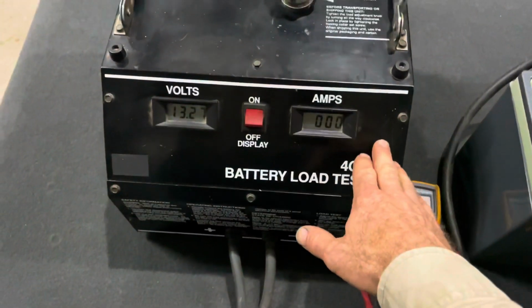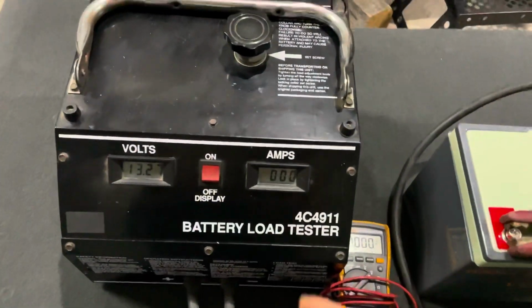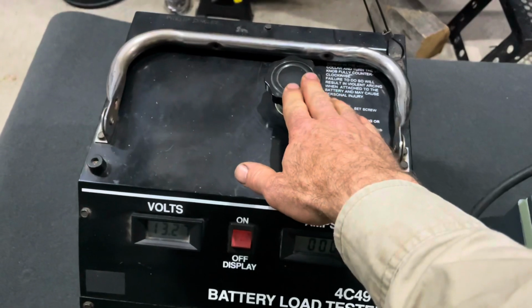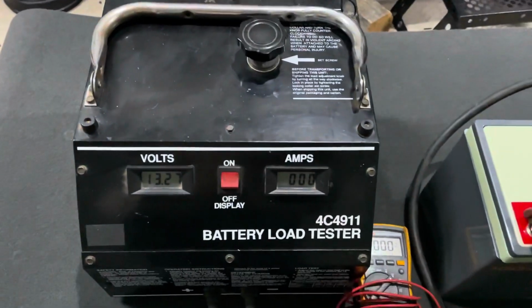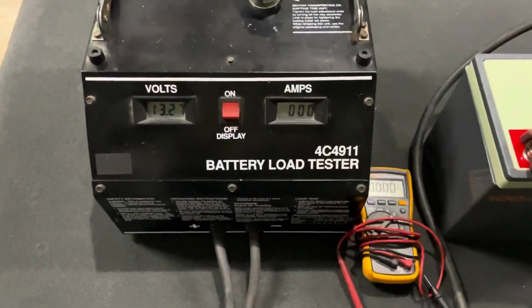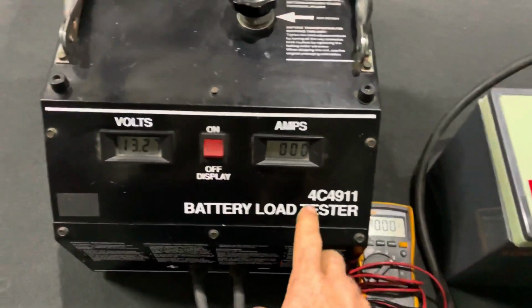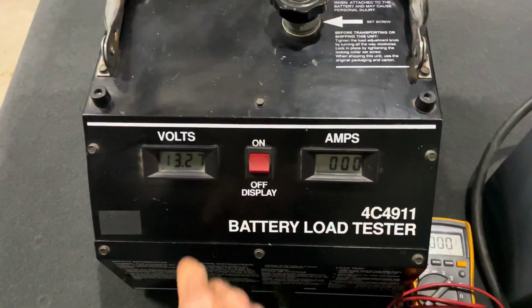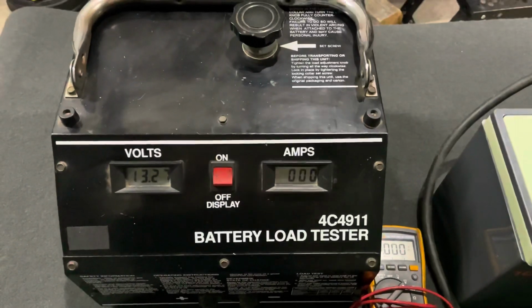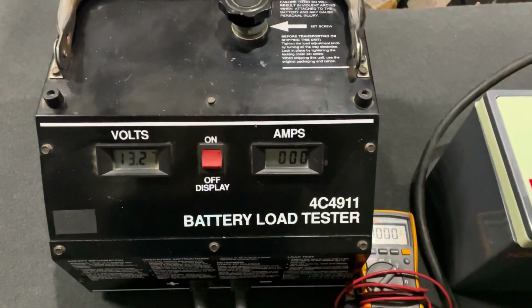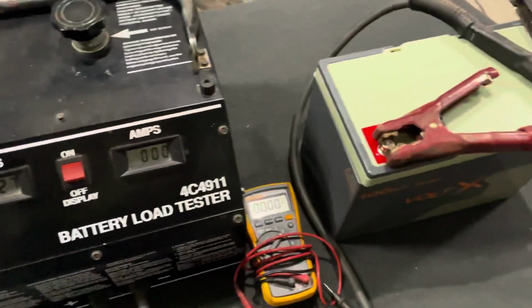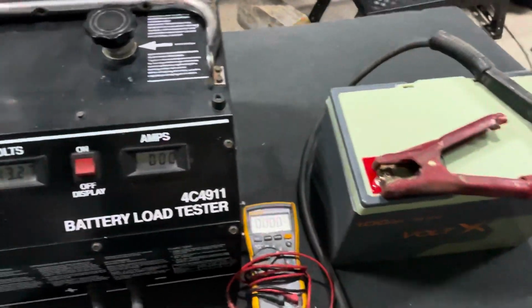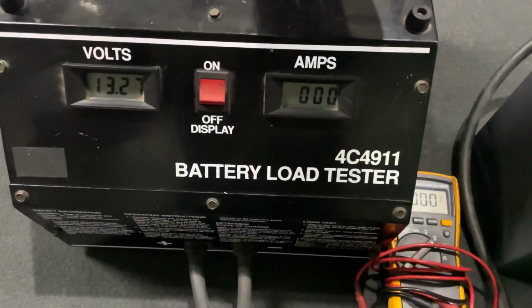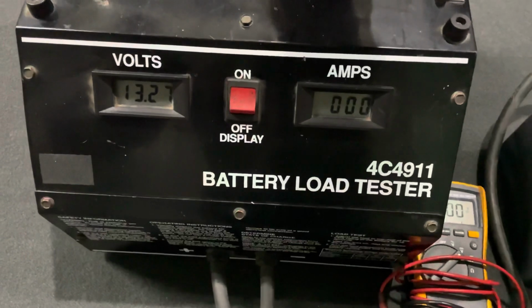I'm going to use a carbon pile battery load tester. You wind in this knob, which clamps the carbon pile tighter and allows it to draw current off the battery. The amps increase on the display, and the volts go down as the amps go up. Let's see if we can let some smoke out of this battery or have it disconnect. It's got a fan in it, so it'll get noisy once that cuts in.